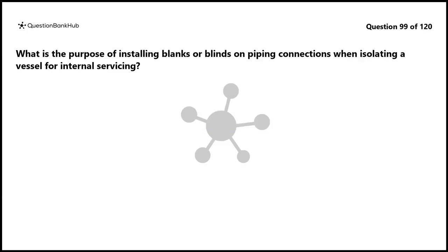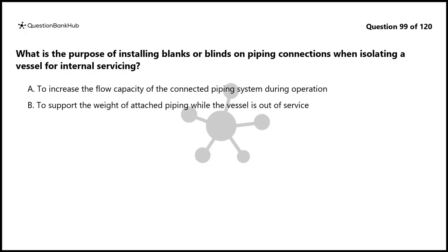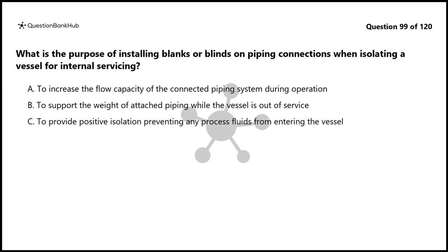Question 99. What is the purpose of installing blanks or blinds on piping connections when isolating a vessel for internal servicing? A. To increase the flow capacity of the connected piping system during operation. B. To support the weight of attached piping while the vessel is out of service. C. To provide positive isolation preventing any process fluids from entering the vessel. D. To protect the pipe flanges from atmospheric corrosion during maintenance.